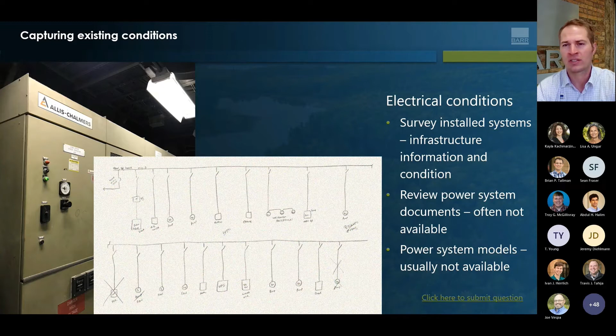However, normally we start out with a hand sketch, such as what you see on the screen here, and then gathering information in the field. So when we gather information, we start at the main substation, walk down through smaller substations, through the switchgear, MCCs, follow busing and wiring, and finally down to the equipments and the other loads such as lighting. Gathering this information in the field, then we produce an electrical power model using the power softwares I mentioned earlier.